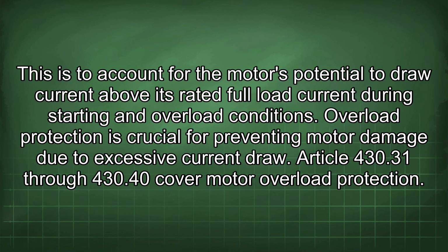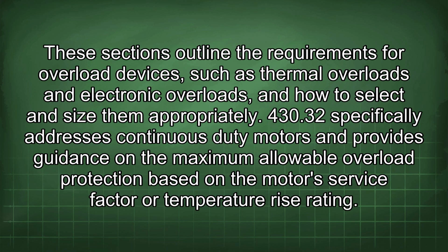Article 430.31 through 430.40 cover motor overload protection. These sections outline the requirements for overload devices, such as thermal overloads and electronic overloads, and how to select and size them appropriately. 430.32 specifically addresses continuous duty motors and provides guidance on the maximum allowable overload protection based on the motor's service factor or temperature rise rating.